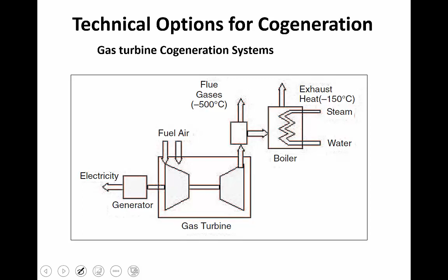If the heat output is less than that required by the user, it is possible to have supplementary natural gas firing by mixing additional fuel into the oxygen rich exhaust gas to boost the thermal output more efficiently. This is one type.